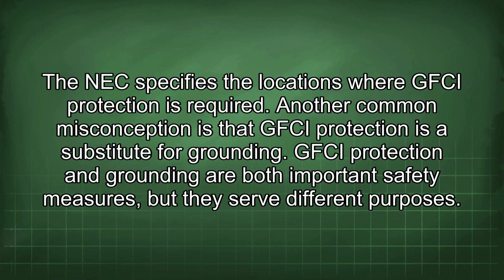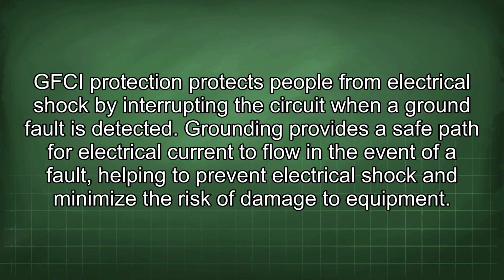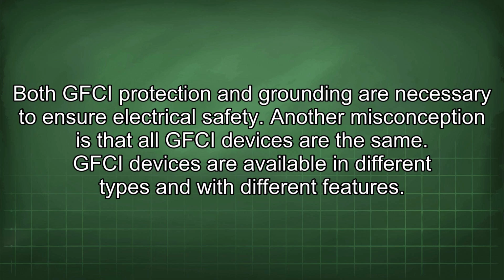Another common misconception is that GFCI protection is a substitute for grounding. GFCI protection and grounding are both important safety measures, but they serve different purposes. GFCI protection protects people from electrical shock by interrupting the circuit when a ground fault is detected. Grounding provides a safe path for electrical current to flow in the event of a fault, helping to prevent electrical shock and minimize the risk of damage to equipment. Both GFCI protection and grounding are necessary to ensure electrical safety.